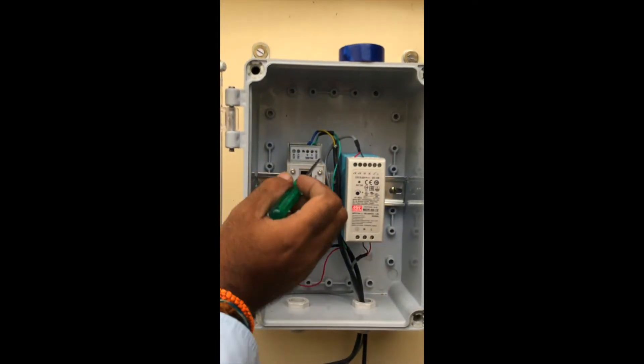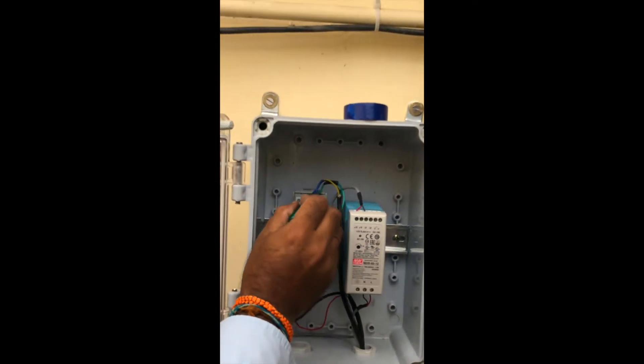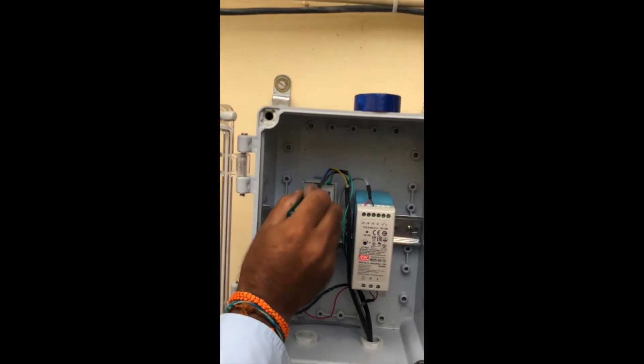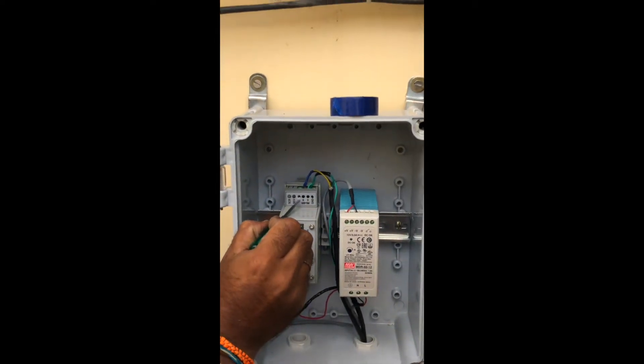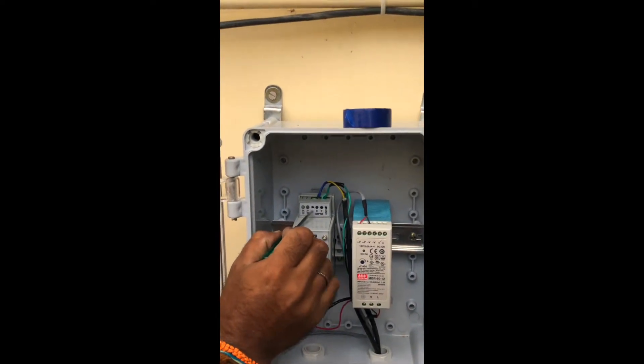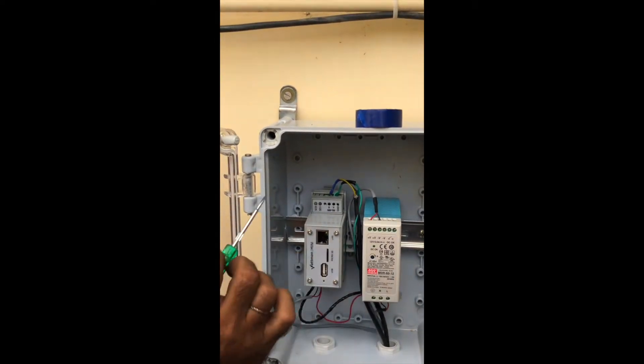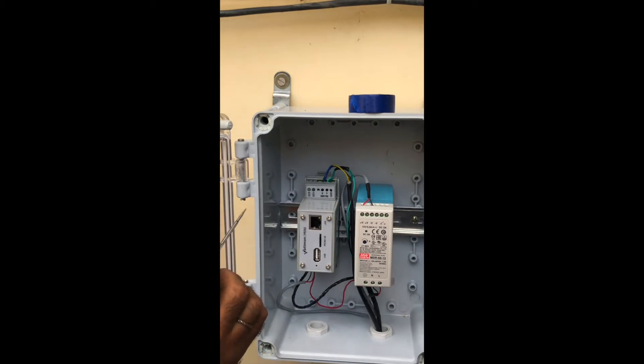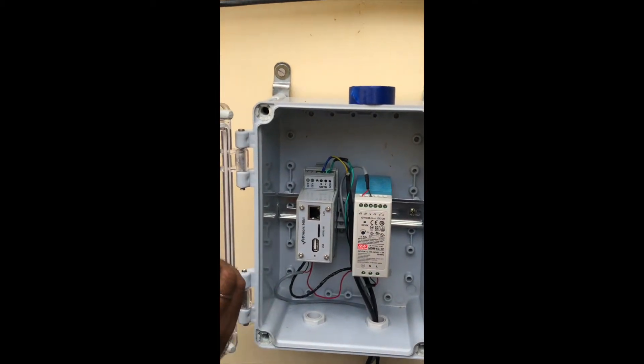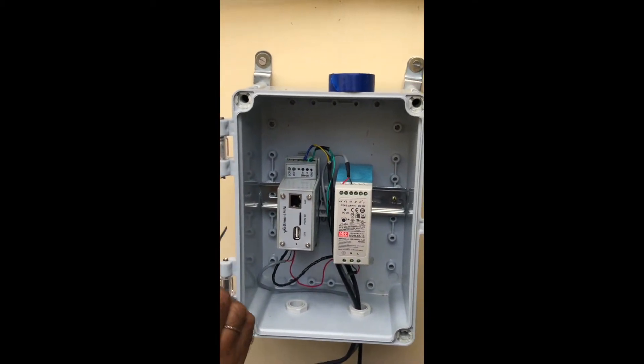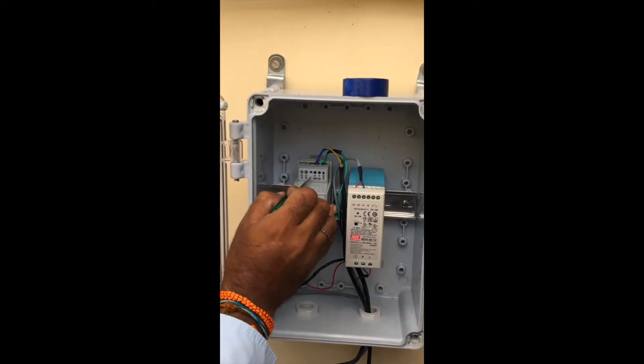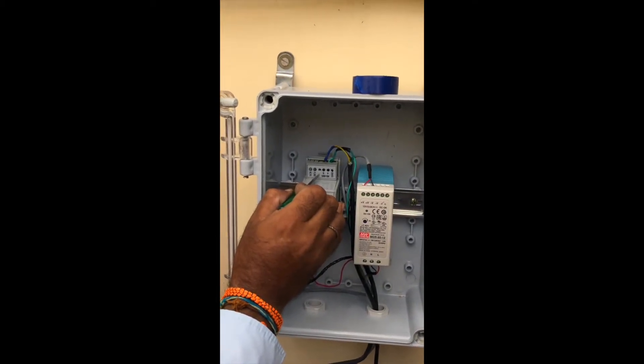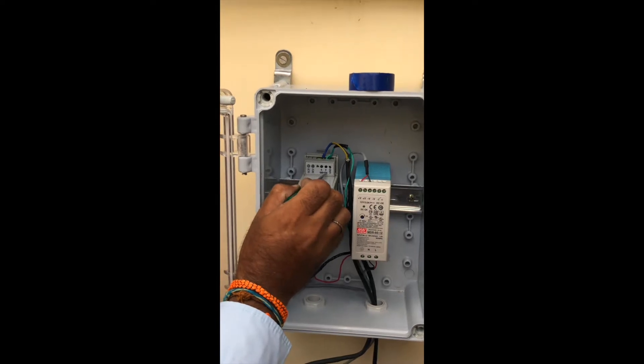After the power connections, we will come on to the communication wiring. The B in the logger represents RS 485 plus, and A in the logger represents RS 485 minus.